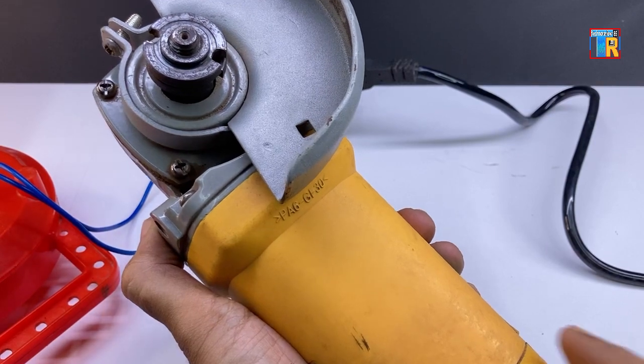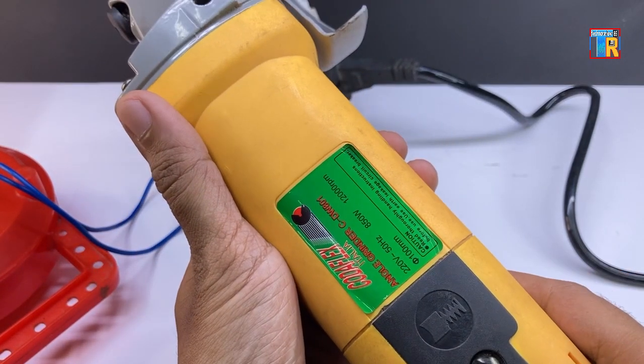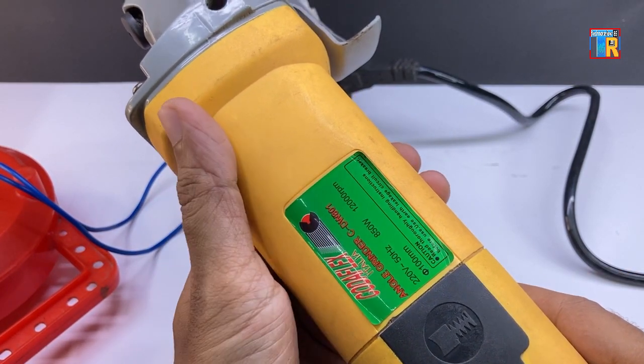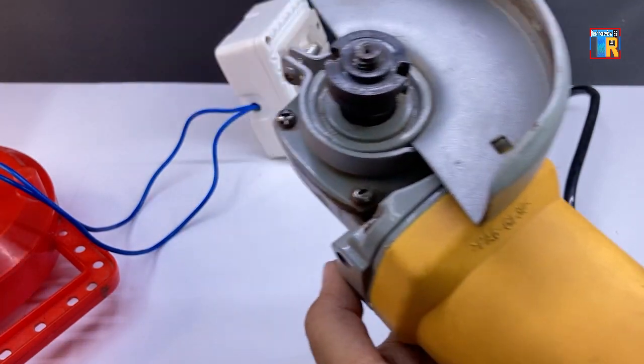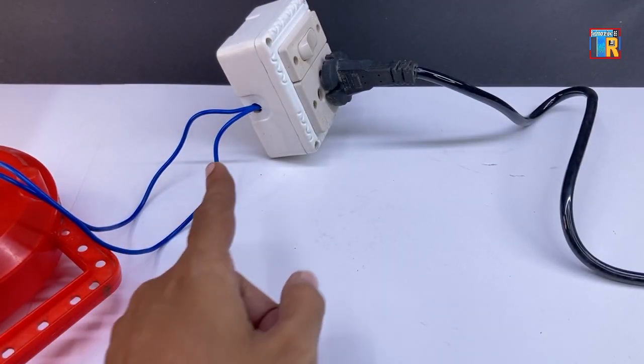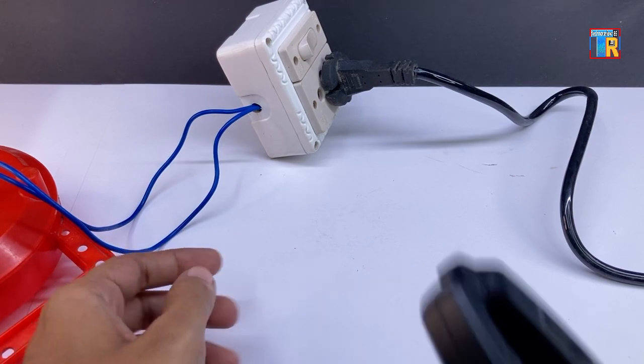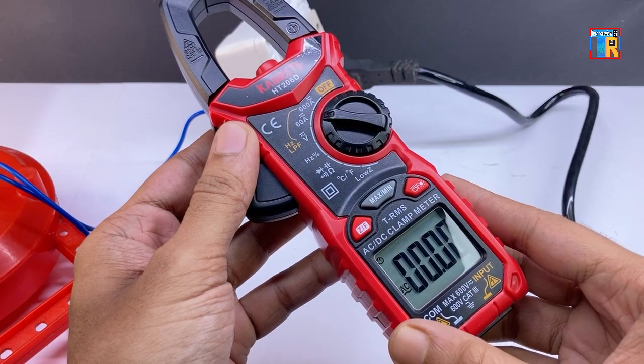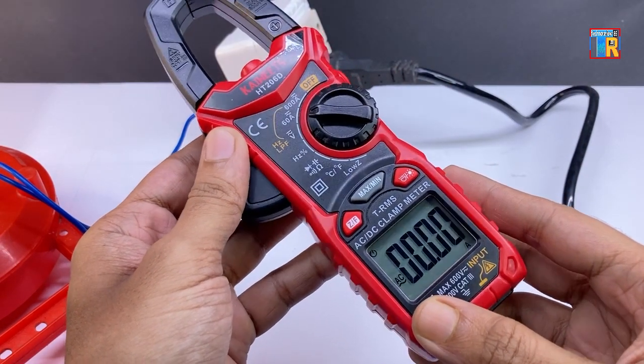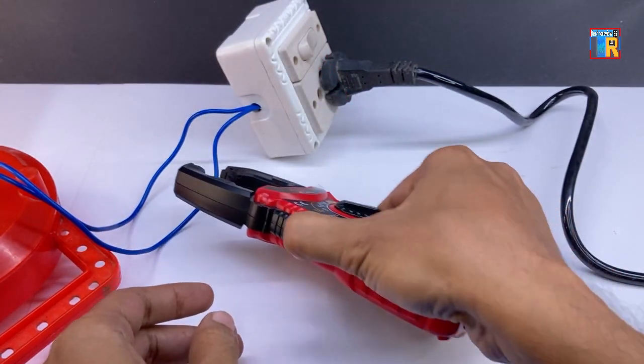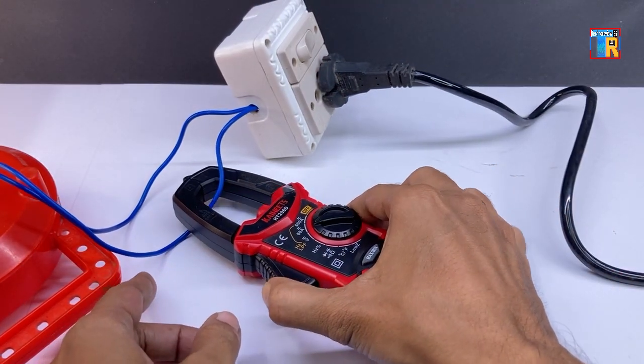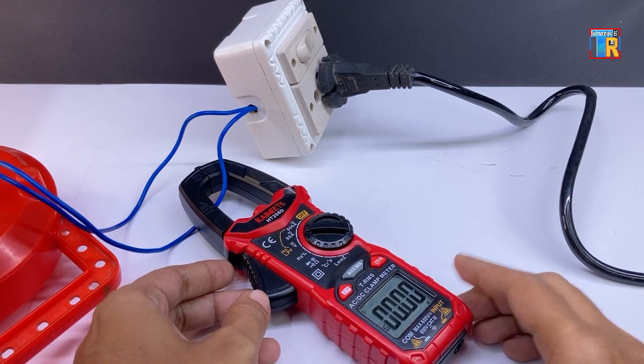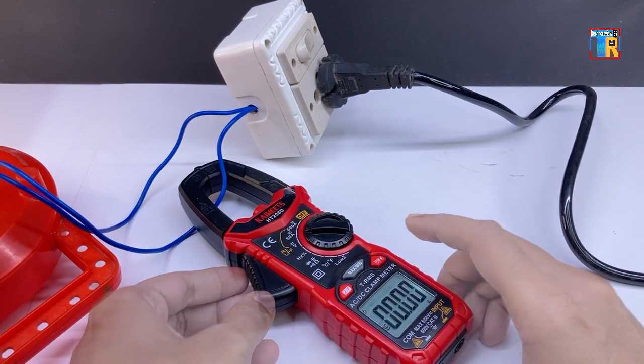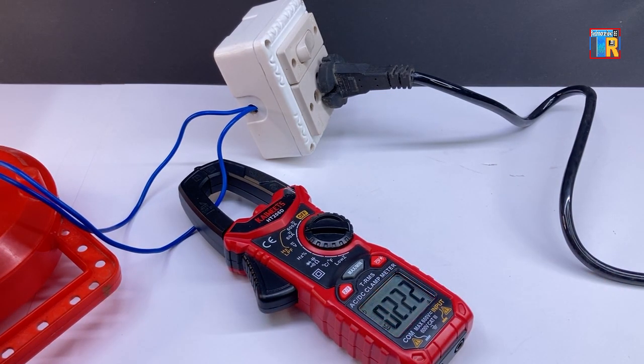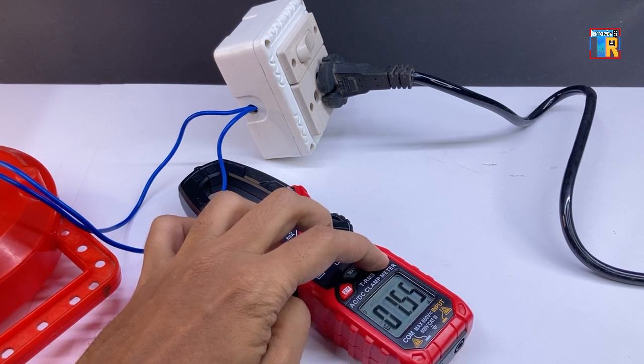I will test the AC load of this angle grinder. It is 850 watts. To test ampere using any clamp meter, you have to use a single wire, not double wire or insulated wire. The meter is set up with AC ampere mode. It is showing about 1.5 ampere.